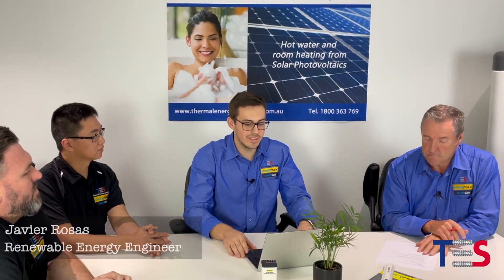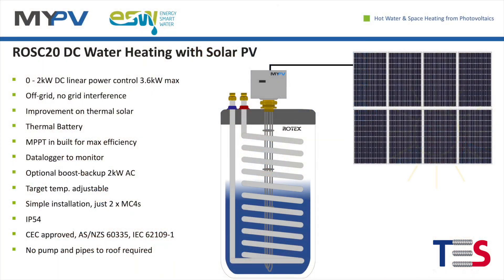Thanks John. So it's very simple — it's just an off-grid product. Basically, dedicated PV panels connected up to 3.6 kilowatts directly to the ROSC20. We make it very easy for installers — it's just two MC4s. Inside the unit there is an MPPT tracker, so we make sure that the panels are always working at maximum power. And if there is no solar, you can also connect the AC boost.